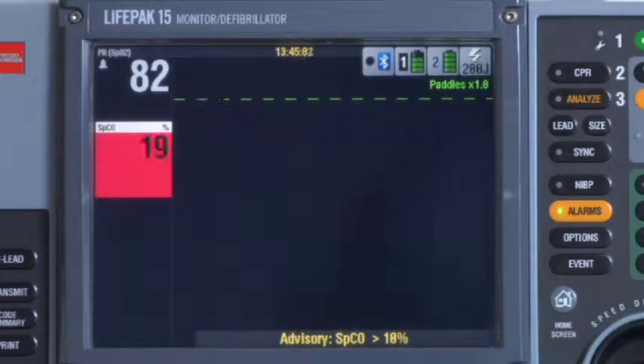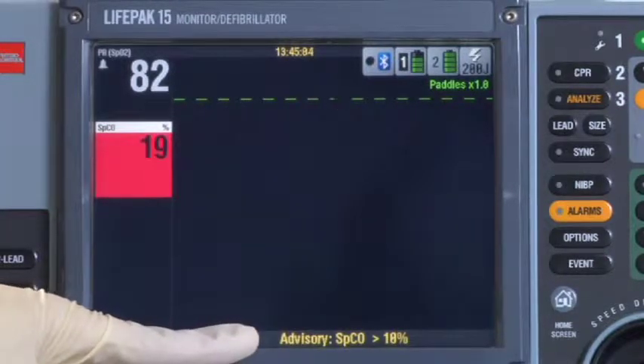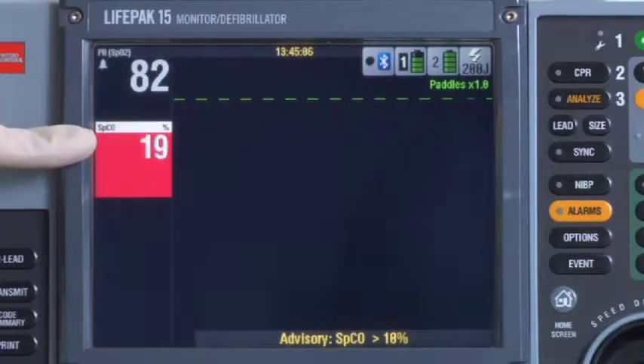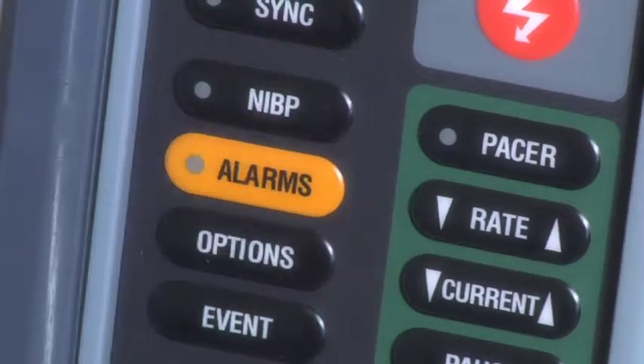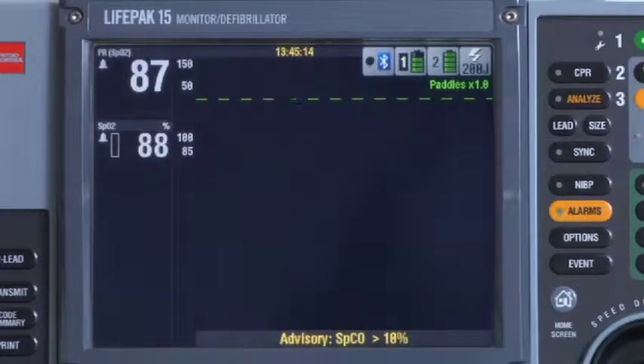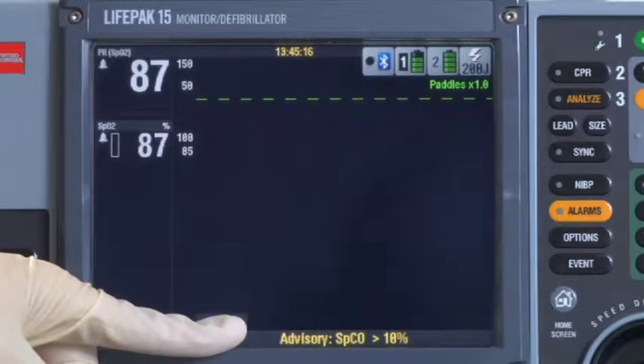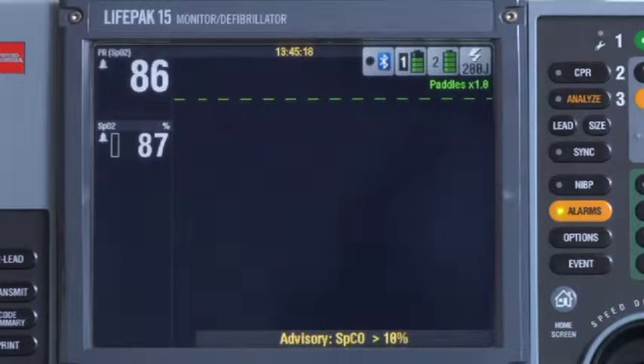There's an alarm tone, an advisory message, and the elevated value starts flashing here instead of the SpO2. To acknowledge the advisory, press alarms. The SpO2 replaces the CO value, but the advisory message stays on the screen until the value drops below 10%. The SpMet advisory works the same way.